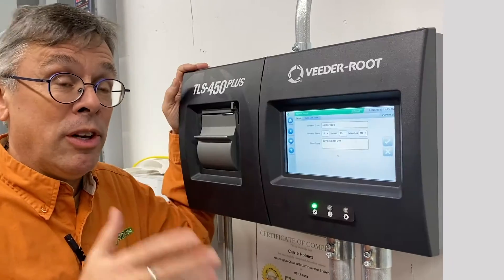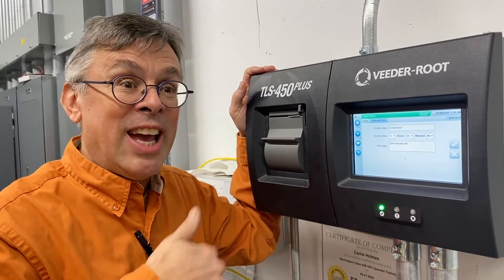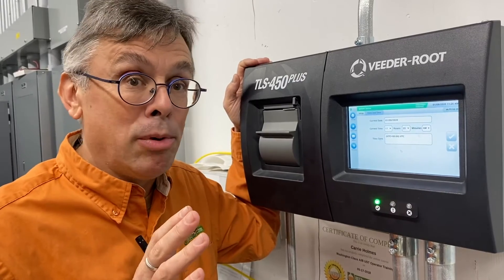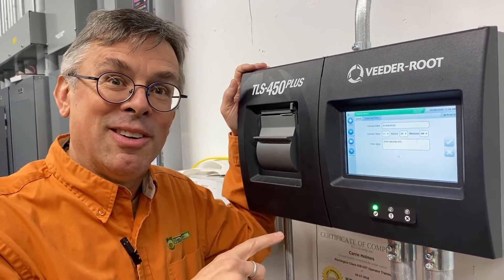This system is actually wide open, and so if you have a Veeder-Root TLS-450 PLUS, you want to make sure you can't do what I just did, which is to get in and have the ability to change the setup features. That'll mess up your tank system completely. This has been Thomas at UST Training. Please don't do this, and this has been a Tank Savvy Minute.